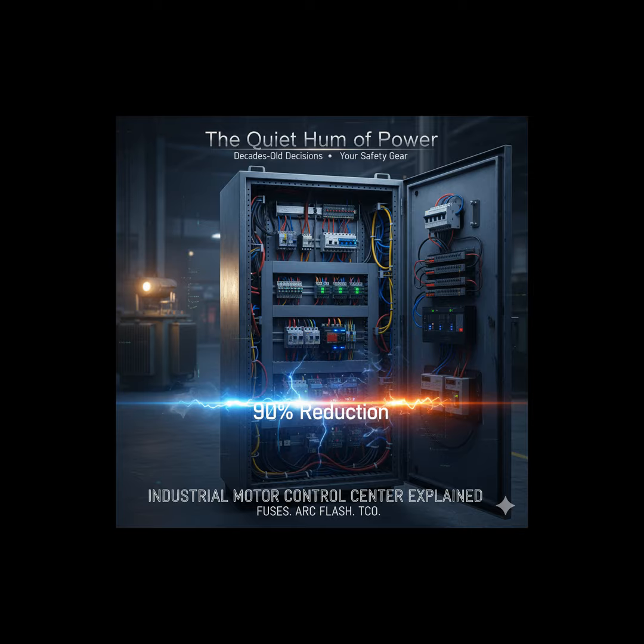They're perfect for constant torque loads like large conveyors. So the soft starter is just about being nice to the motor during acceleration. If you need to actually modulate the speed while the system is running, that's where the VFD comes in. Exactly. The variable frequency drive, or VFD, or AC drive, regulates both voltage and frequency simultaneously using an inverter section. By varying the frequency, you control the motor's speed throughout its entire operation, not just its startup. And this is essential for? For variable torque applications, pumps and fans, where slowing down saves immense amounts of energy. For example, reducing a pump speed by just 20% can cut its power consumption by almost 50%.